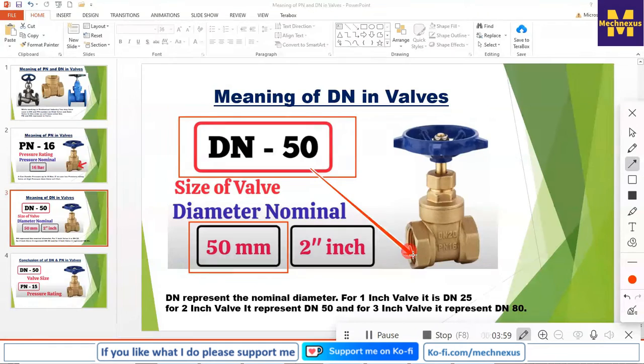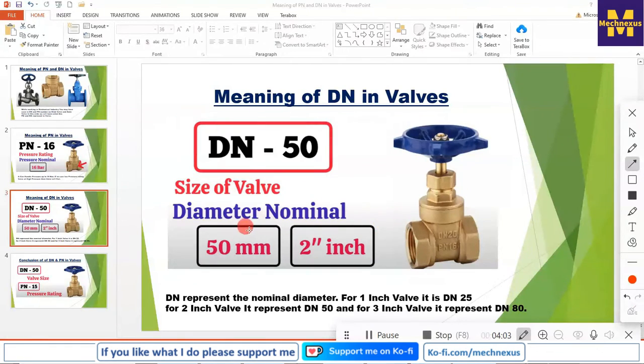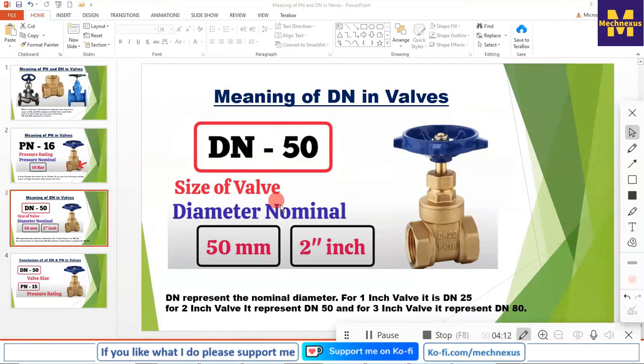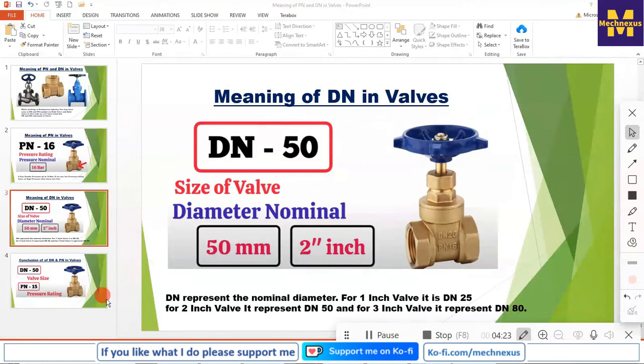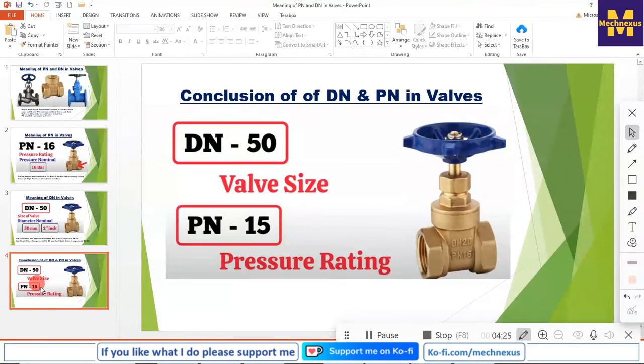If it is DN 50, that means there is a 50 mm bore, as you can see here. If we express this in inches, it will be a 2-inch valve. So if we are going to purchase a DN 50 valve in metric, we simply say it is 50 mm. But if we refer to ASME standard or inch standard, then it will be called a 2-inch valve.